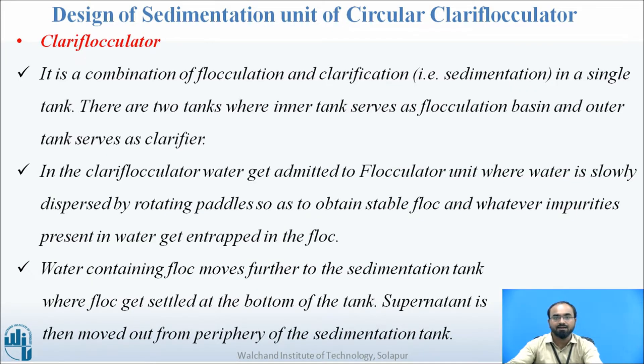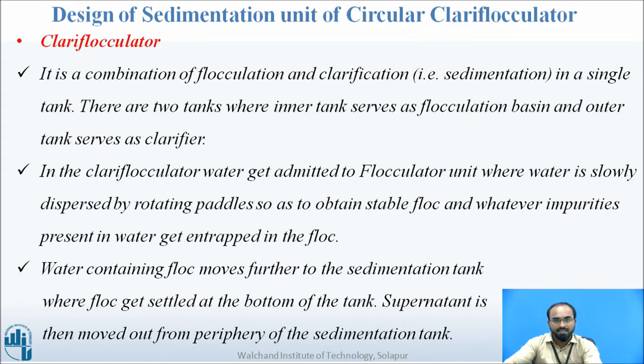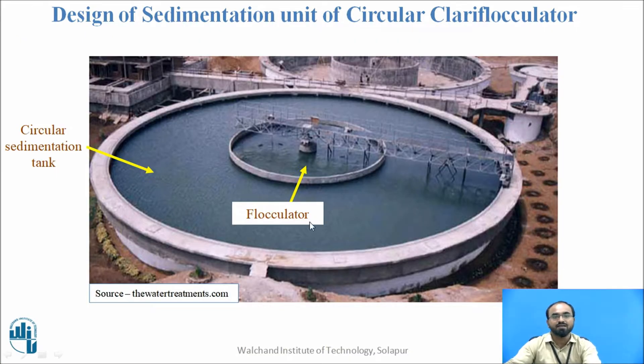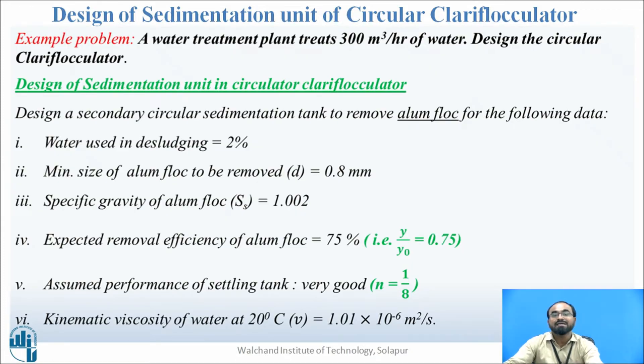We had seen this slide earlier also in the design of a flocculation unit of a circular clariflocculator. Basically, a clariflocculator is a combination of flocculation and sedimentation unit, where first the water will be coming into the flocculation unit where large amounts of impurities will be agglomerating with the help of slowly moving paddles, forming big size flocs. Then the water is shifted to the clarifier or outer unit, where these flocs will settle due to gravity. We are going to design that outer part today, for a flow rate of 300 meter cube per hour.